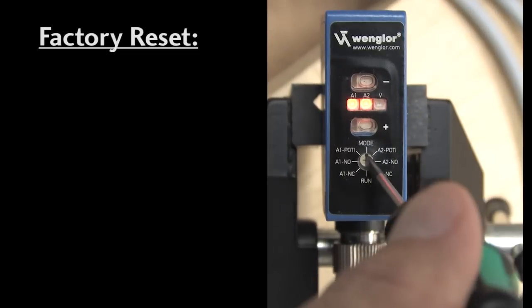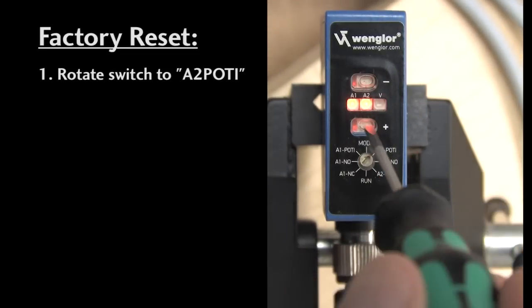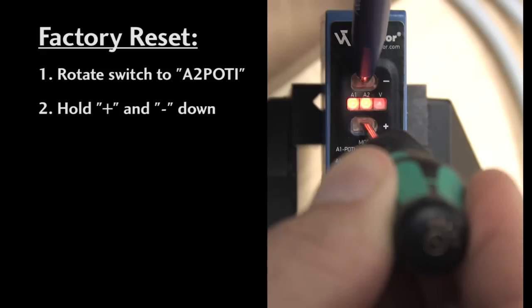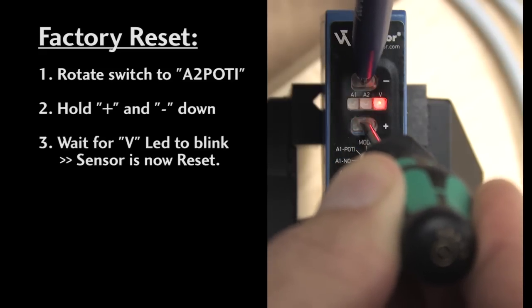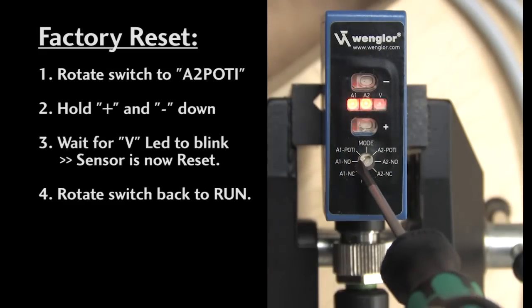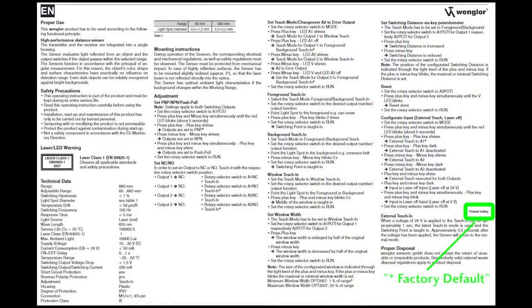To get the sensor back to factory reset, rotate the selector to the A2 POTI setting and hold down both the plus and minus keys until the red V LED blinks. Set the selector back to run and the sensor's reset to factory default. What are the factory defaults? Anything with an asterisk next to it on the product insert.